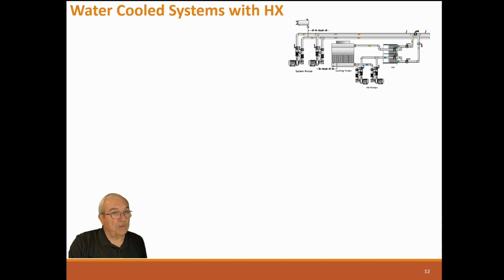And these are cleanable, of course. And then we have this system just like the others, whether it might have a boiler downstream or not. But this is the system they support. So it may not be intuitive, but the cost of this heat exchanger and the cost of these pumps and the cost of that cooling tower are just slightly higher than the cost of one fluid cooler.